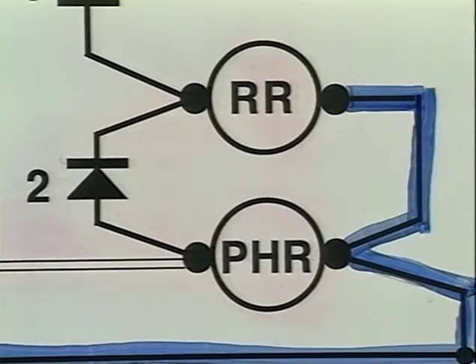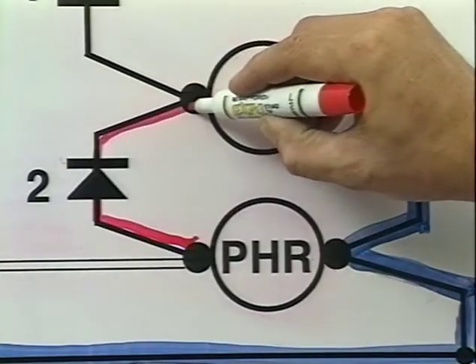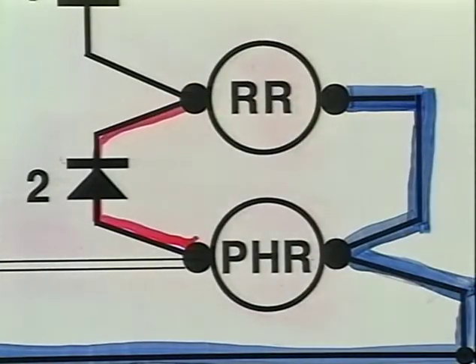Let's start with the diode number two between the preheat relay and the run relay. If the diode shorts closed, the engine runs, but the preheat elements remain energized and will eventually burn out. If it shorts open, the preheaters are energized when the shutdown bypass is pushed.